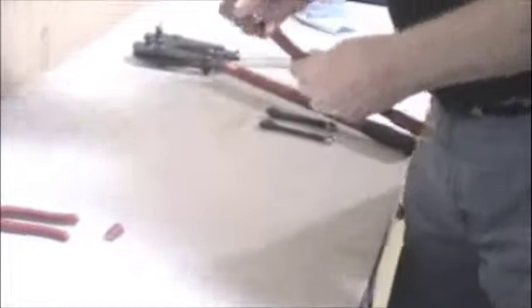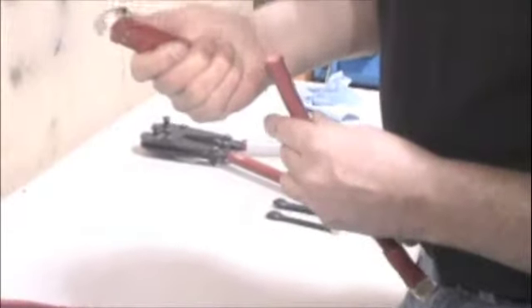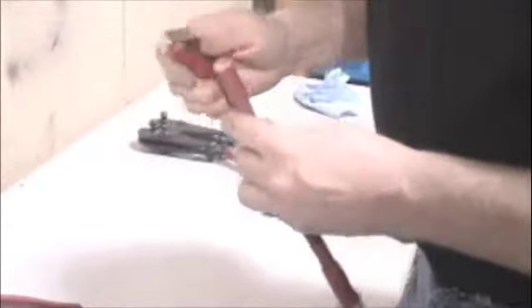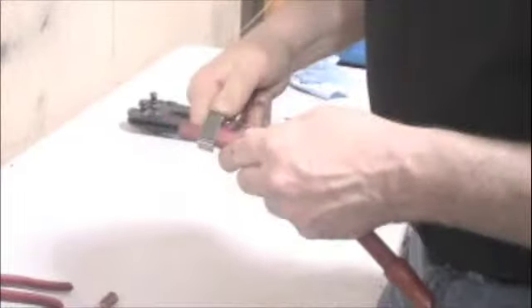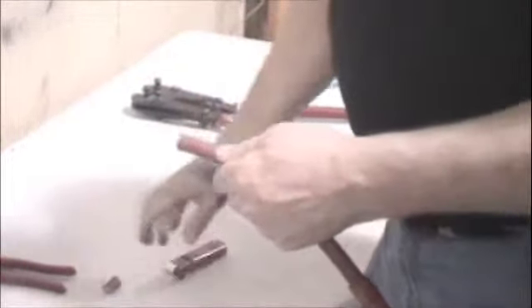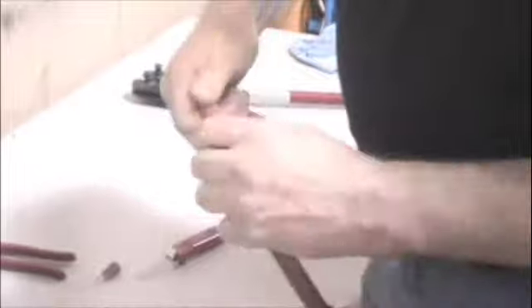Next item is a cable stripper. It's a pretty simple tool, has a razor head on it that's adjustable for different depths and what this is going to do is cut the insulation back. Basically set the knife to the proper height and rotate it around the jacket and it's going to remove the cable jacket or the insulation jacket.